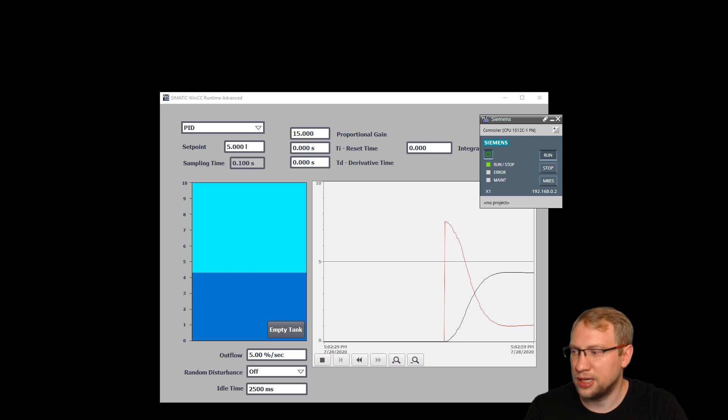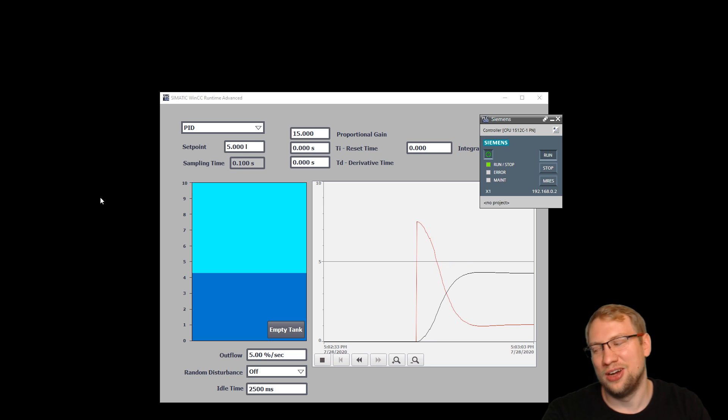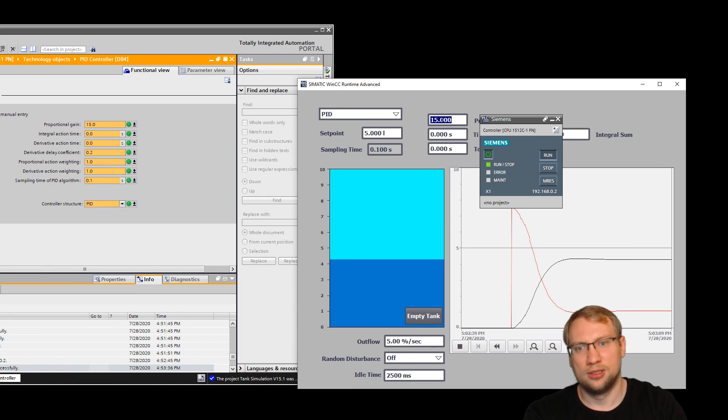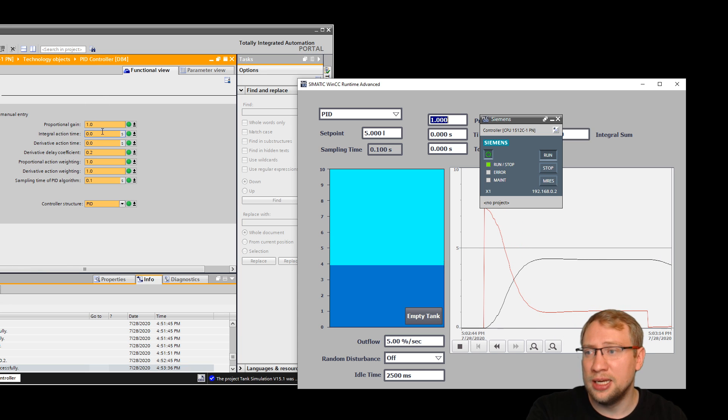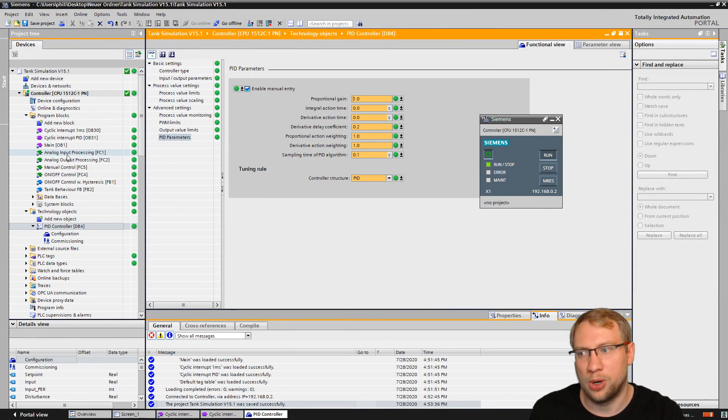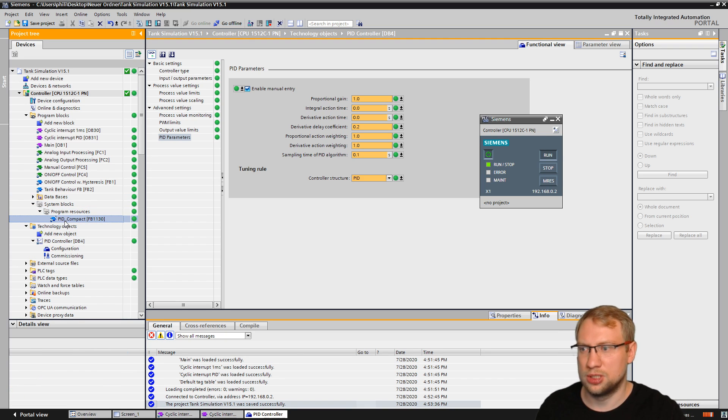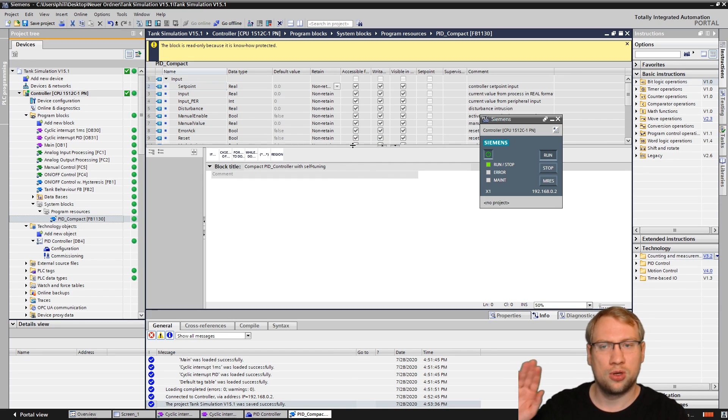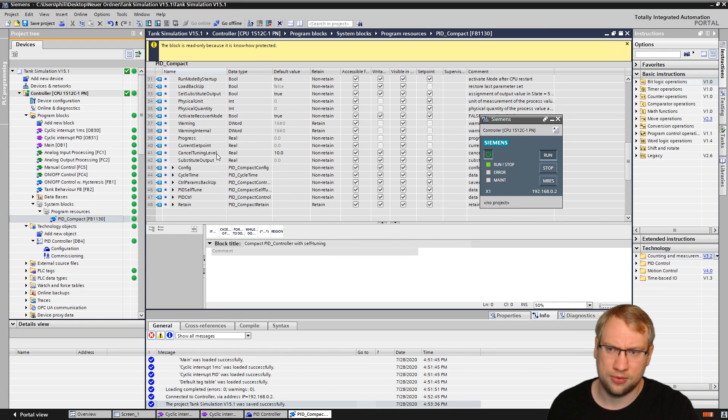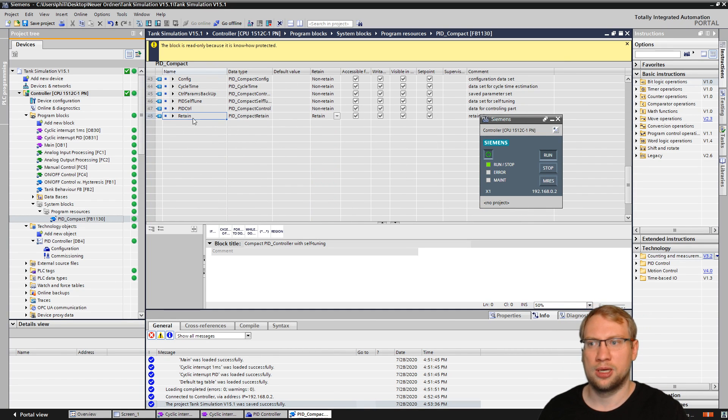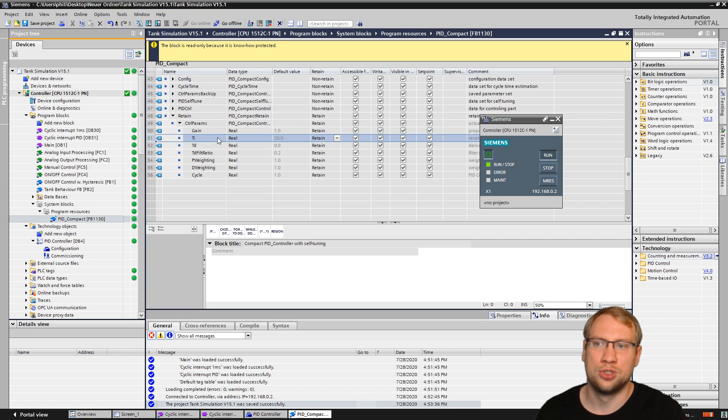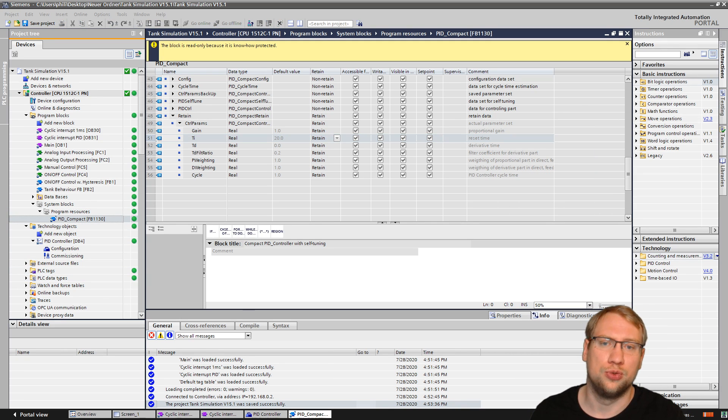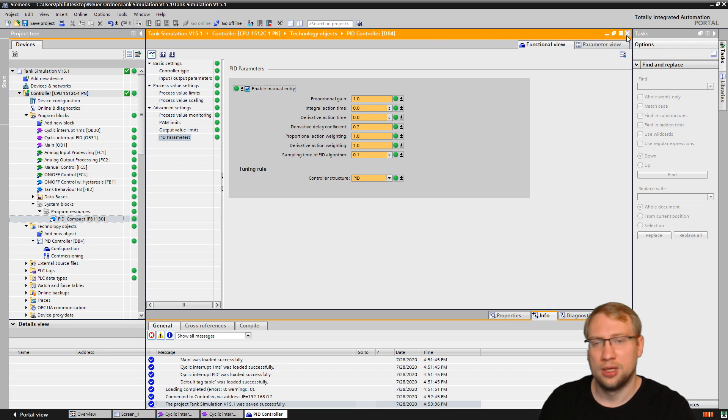So the question that I get a lot is actually the following: How do you get it on your HMI? And also, it's on the HMI here. And if I change it on the HMI, I can actually change the value and it really changes in the PID Compact block, right? So it's there. It's pretty strange because I don't find it anywhere. Well, there is. If I go under system blocks, program resources, we've got the PID Compact block. This one is automatically added when you use the PID Compact in your program. It's the function block that needs a system function block. And there we have all these parameters up here. And that's basically you can get them from here. Basically if I want, I can just go in somewhere and drag and drop one and use it on my HMI. That's one way.